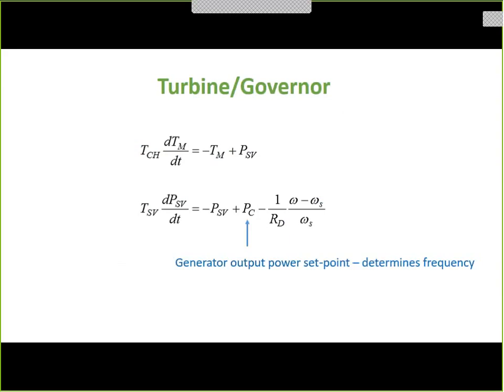So there's a command power, P, but then there's an automatic part. If the frequency gets too high, omega is bigger than omega S. That's a positive number, times a minus sign is a negative number. It will shut the steam valve, because if the frequency is too high, the machine is turning too fast. So it'll shut the steam valve down, which in turn shuts down the torque to the generator.